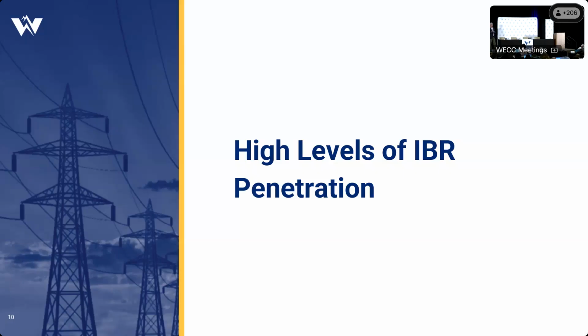So these resources are fabulous. They perform well. The batteries are really, really interesting. They perform phenomenally well with fast frequency response. We had a very large event, several large events this summer that were loss of load events, and our interconnection frequency response was probably twice as good as we expected it to be. A lot of that is due to IBR footroom. We always think of headroom on units. IBRs always have footroom. So when we have a loss of load event, we tend to perform really, really well.